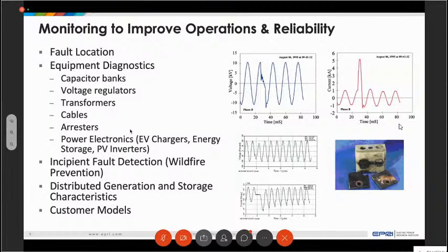Of course, fault location is probably the one application that pays for itself almost immediately. Having monitoring even at the distribution substations can help locate faults on the distribution system, so we can send crews out to repair issues faster and send them right to the fault, which can be very valuable. But it's also possible to identify conditions that don't necessarily cause faults, but could result in faults in the future. We call these incipient faults or arcing conditions.